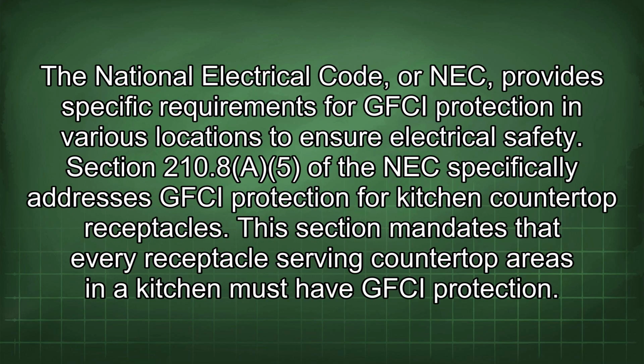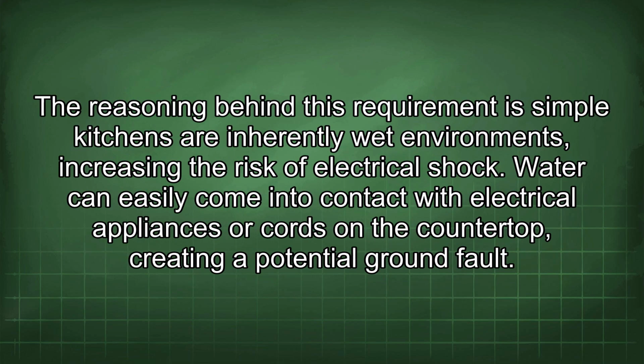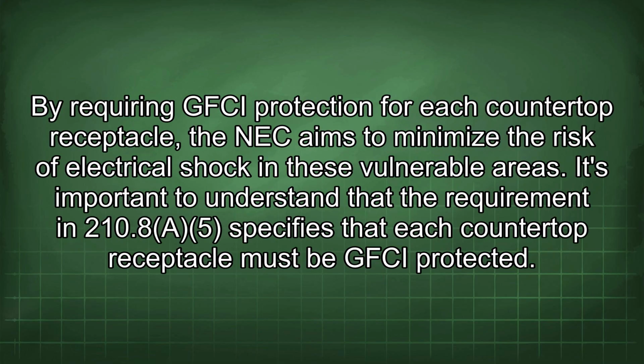The National Electrical Code, or NEC, provides specific requirements for GFCI protection in various locations to ensure electrical safety. Section 210.8(A)(5) of the NEC specifically addresses GFCI protection for kitchen countertop receptacles. This section mandates that every receptacle serving countertop areas in a kitchen must have GFCI protection. The reasoning behind this requirement is simple: kitchens are inherently wet environments, increasing the risk of electrical shock. Water can easily come into contact with electrical appliances or cords on the countertop, creating a potential ground fault. By requiring GFCI protection for each countertop receptacle, the NEC aims to minimize the risk of electrical shock in these vulnerable areas.